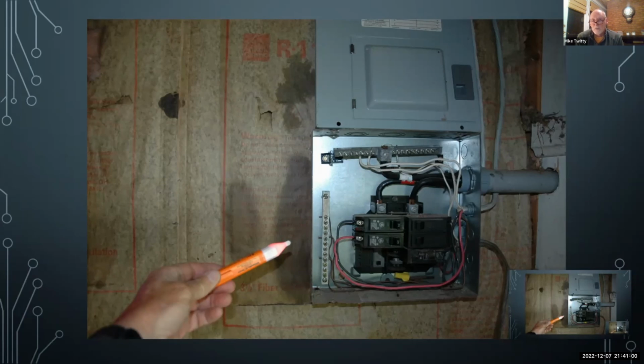Like I say, I always tell people if you're comfortable reading just the voltage at the service equipment, read the incoming voltage. It's going to tell you a lot because there are 208 single phase services out there, and a lot of guys are just blanket putting in their reports. The service is a 240, 120 volt service. You will not know what it is unless you measure it. You can't tell visually by looking at it.